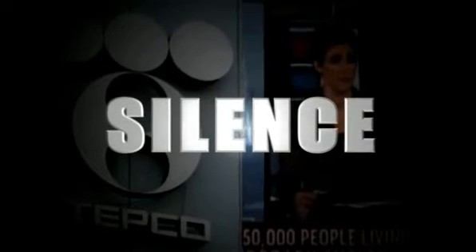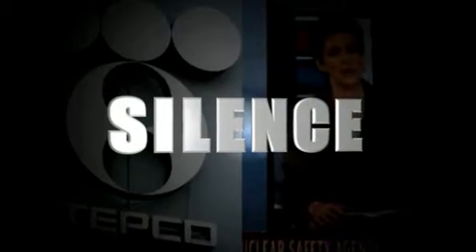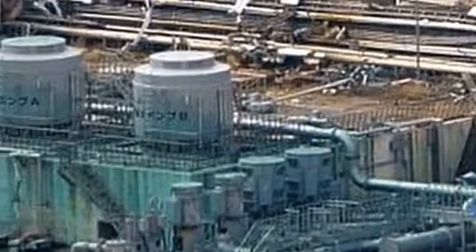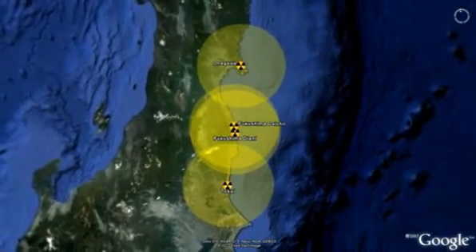Mainstream media isn't talking about that. The nuclear industry is not talking about that either. The diesels were not flooded. What happened was the pumps along the ocean were destroyed, not just for Fukushima Daiichi 1, 2, 3, 4, but at every one of those sites, at least one diesel was knocked out because it couldn't be cooled.